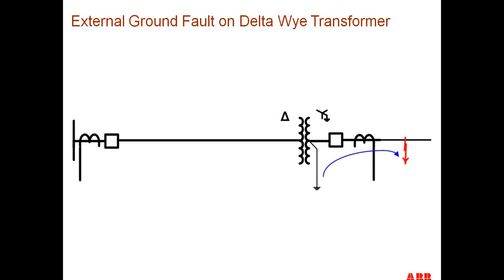So now let's look at the next example. If we have an external fault on the low side of the transformer, now we have current that's the opposite of our inrush problem. Current is flowing on the low side of the transformer through the CT to the ground fault, coming up through the grounded Y winding of the transformer, where we don't see that on the delta side at all.